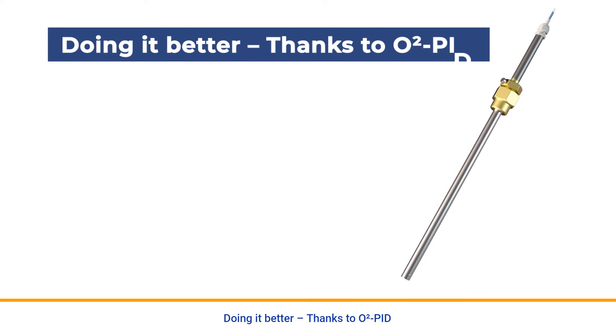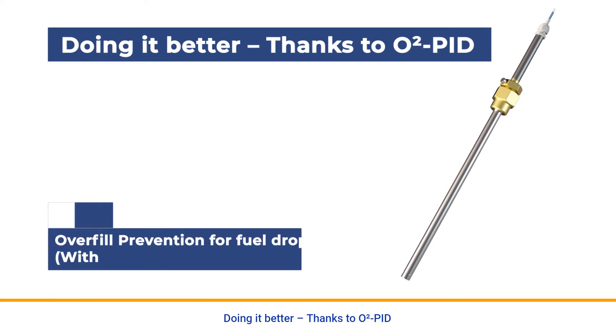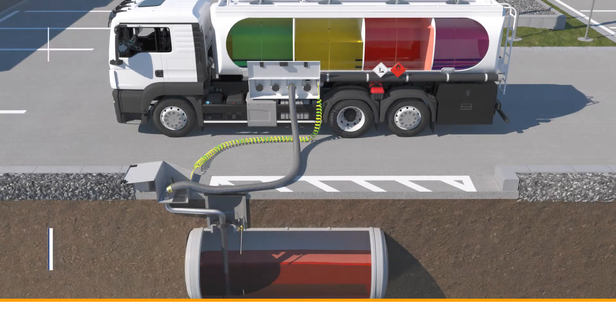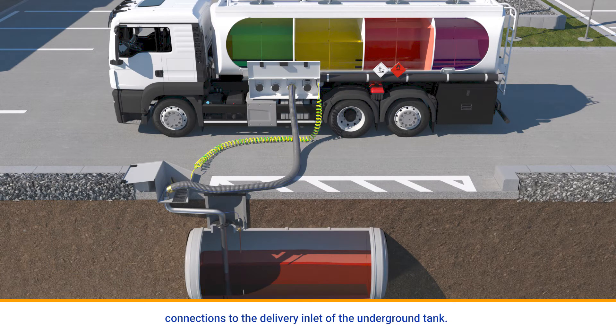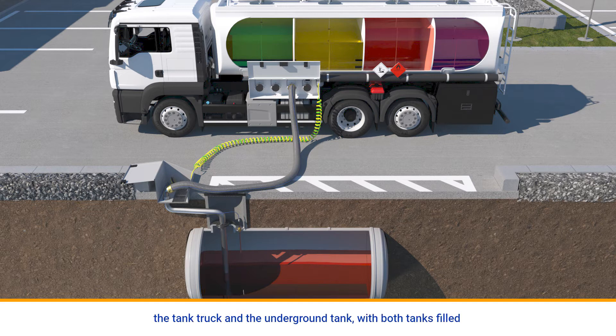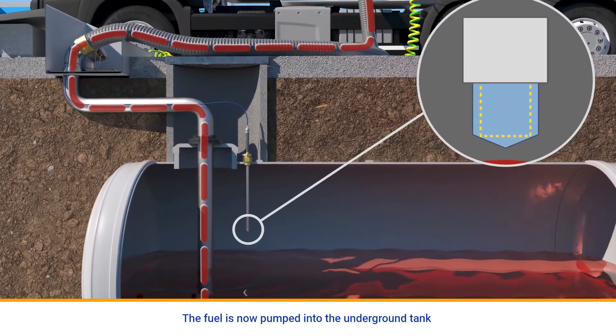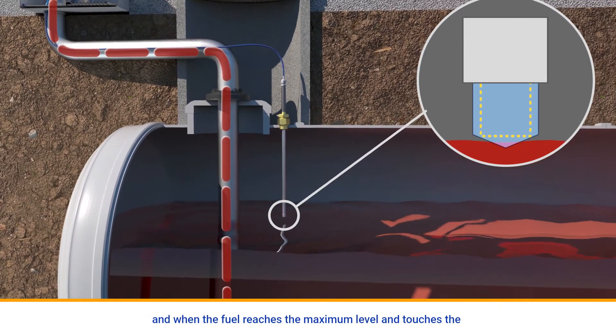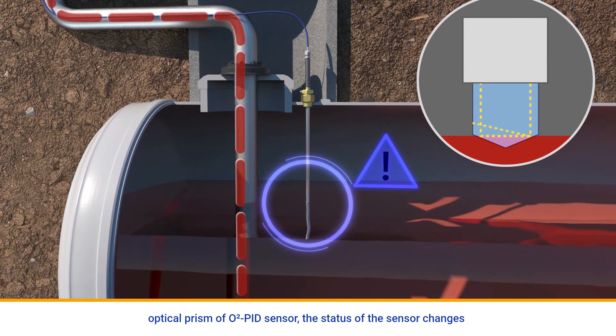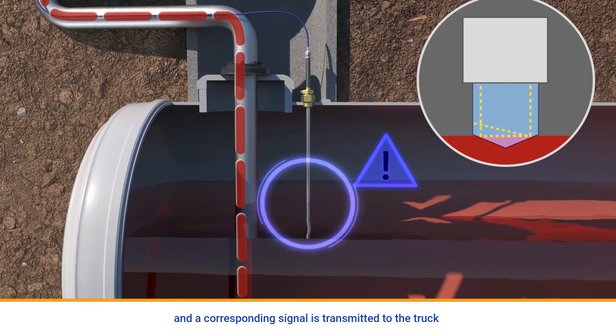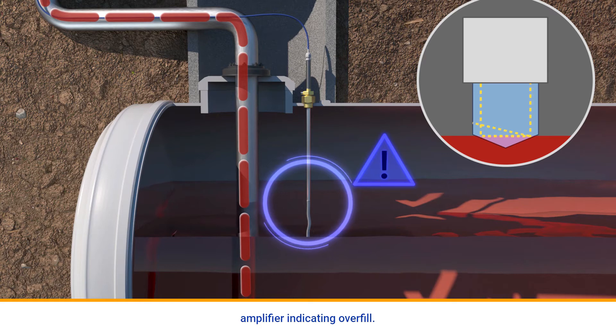Doing it better — thanks to O2PID. Scenario 3: Overfill prevention for fuel drop with O2PID. The O2PID is now installed on the tank with proper electrical connections to the delivery inlet of the underground tank. The electrically conductive hose is correctly connected between the tank truck and the underground tank, with both tanks filled with diesel. The fuel is now pumped into the underground tank, and when the fuel reaches the maximum level and touches the optical prism of the O2PID sensor, the status of the sensor changes and a corresponding signal is transmitted to the truck amplifier indicating overfill.